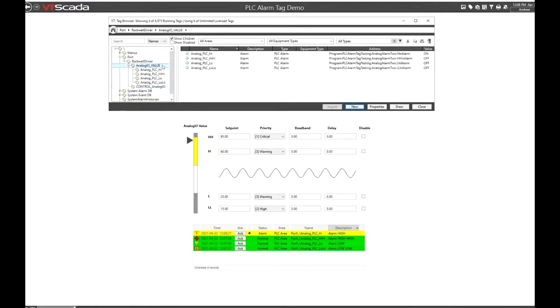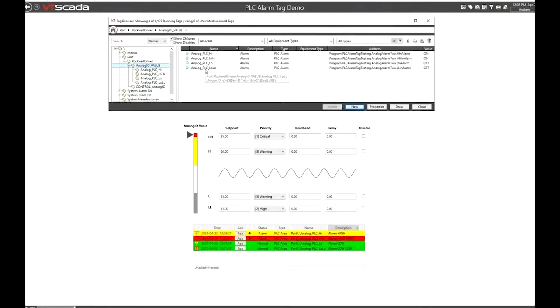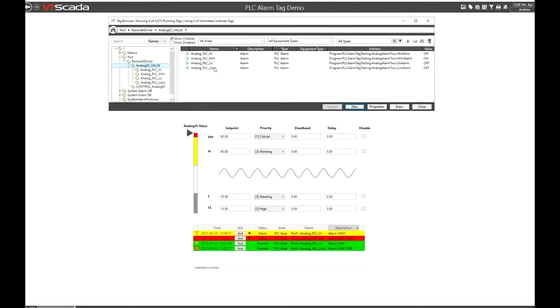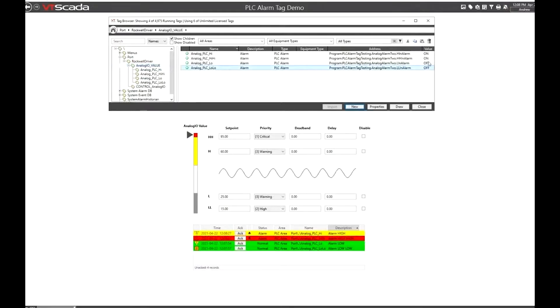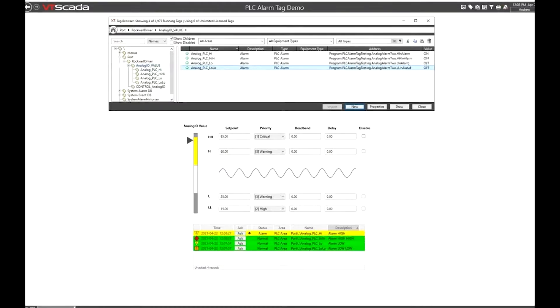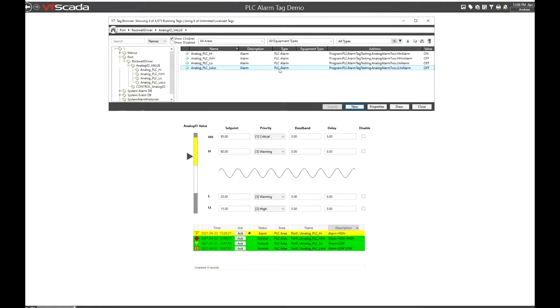And underneath this read I.O. tag, I have four PLC alarm tags which are part of the same alarm block for a high, a high high, a low, and a low low alarm. These we're just reading digital values whether the alarm is on or off in the PLC based on the logic that's being taken care of in that PLC. None of this alarm logic is being handled in VT SCADA.